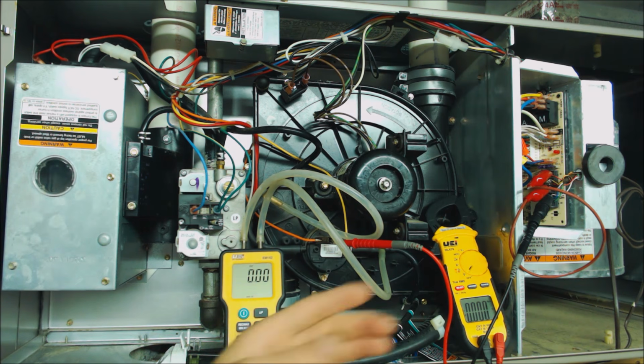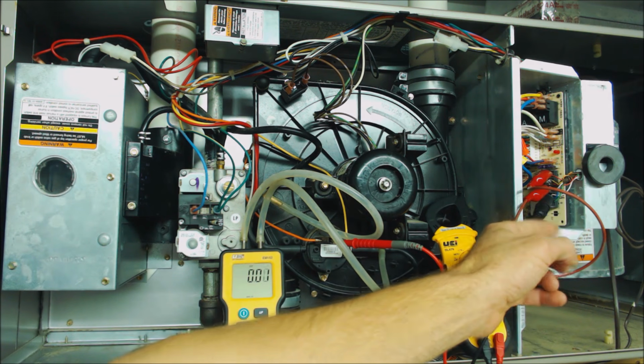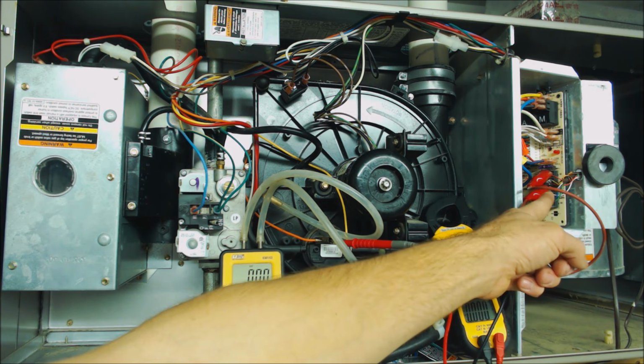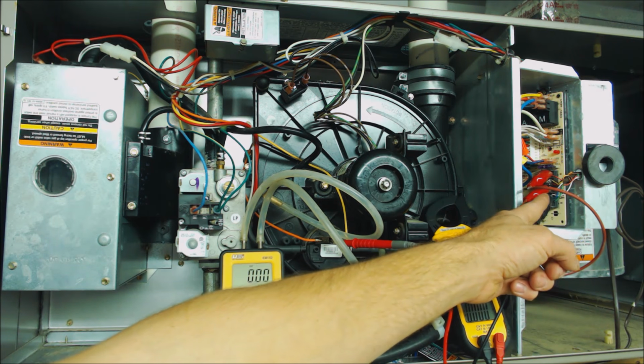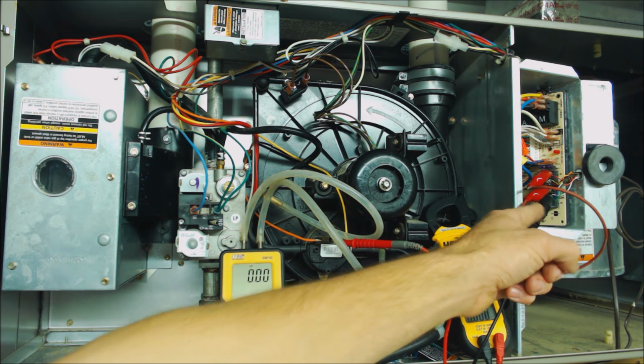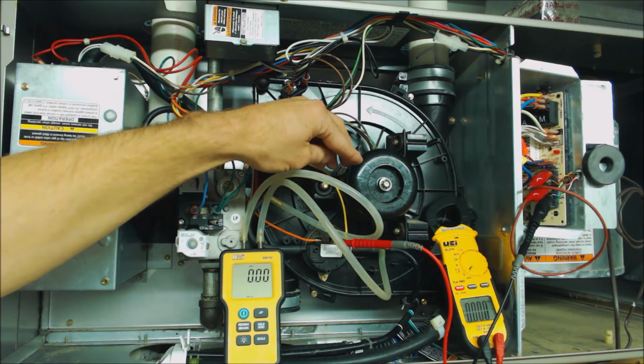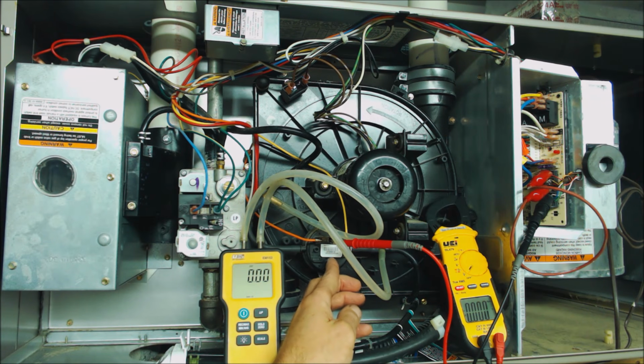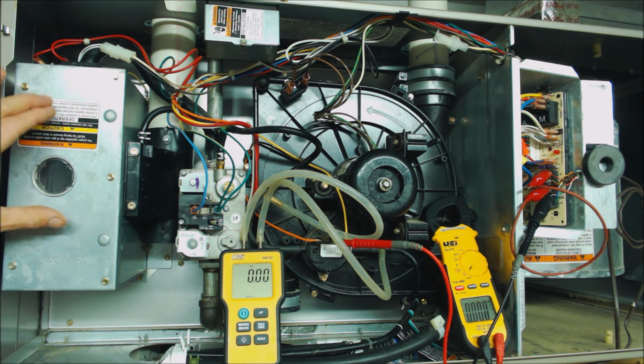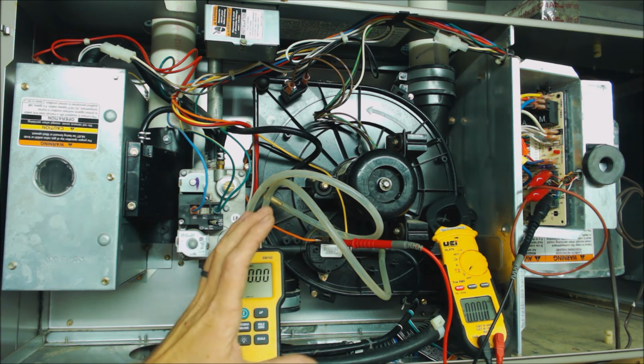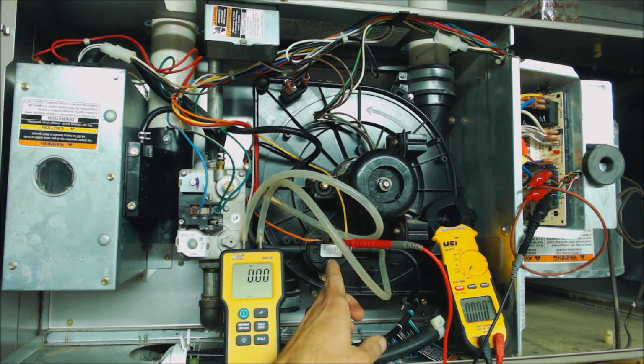So how the whole thing works, when we have a call for heat, we can confirm that we do have a call for heat on the control board by reading voltage from W to C on the terminals. Then after that, what happens is the inducer motor turns on first, then the pressure switch proves that the inducer motor is working and that everything is safe. Then after that, on this one, the hot surface igniter gets powered and turns cherry red.